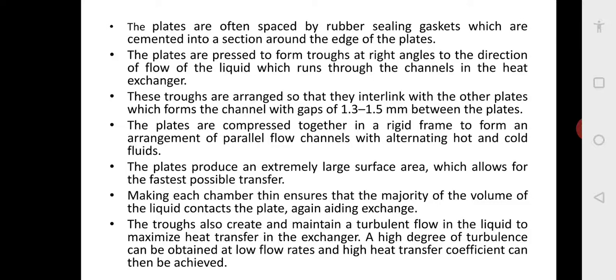The troughs create and maintain a turbulent flow in the liquid to maximize the heat transfer. This turbulent flow increases the convective heat transfer coefficient H. A high degree of turbulence can be obtained even at low flow rates, so a high heat transfer coefficient can be achieved.